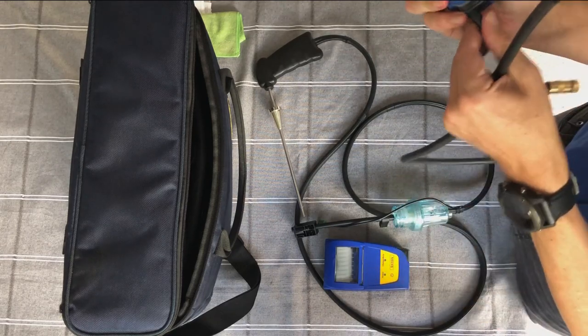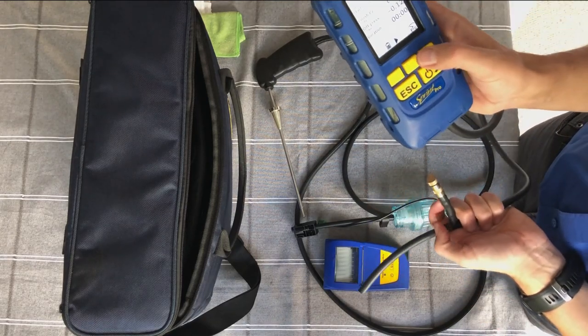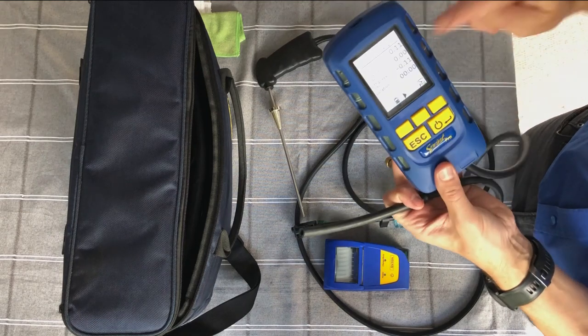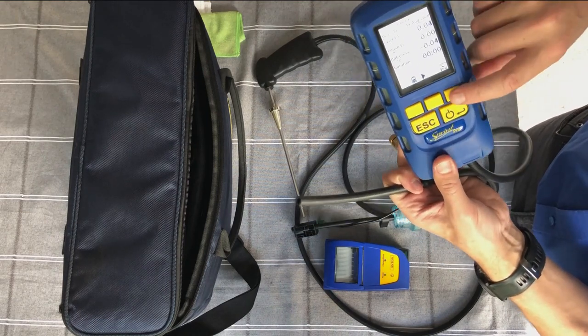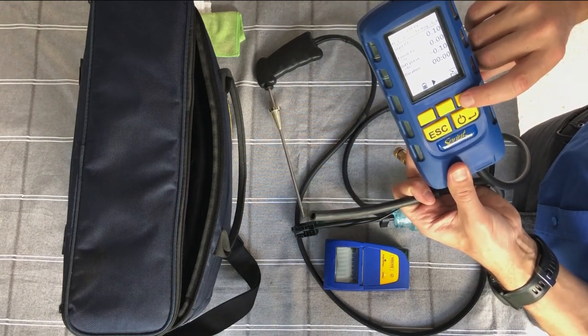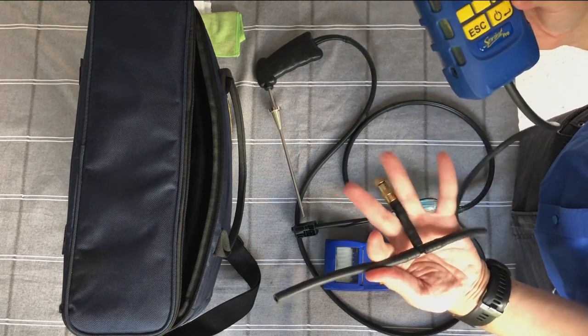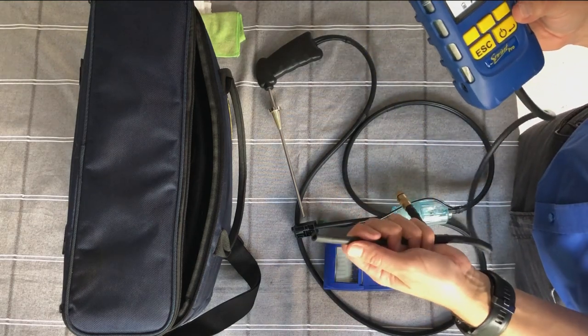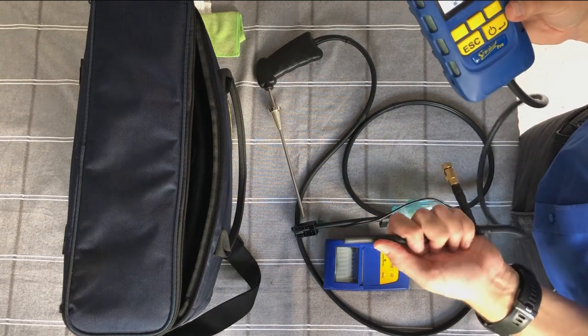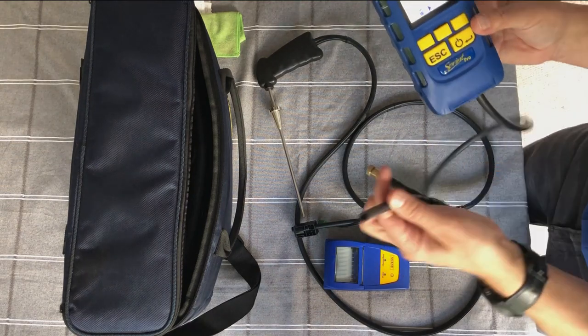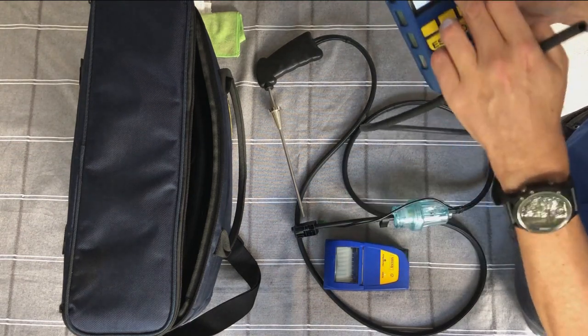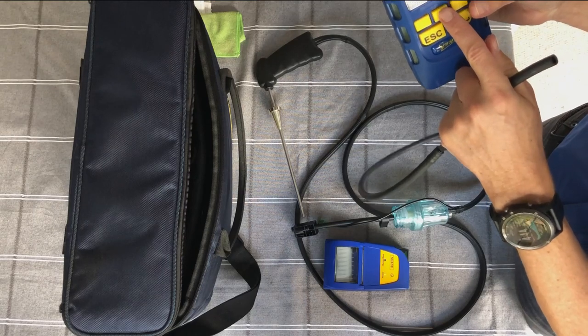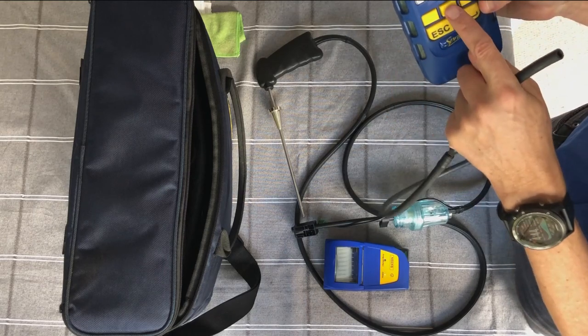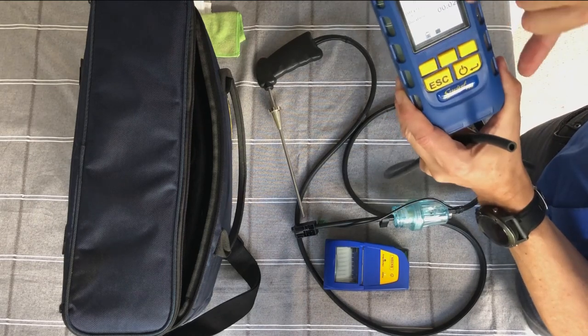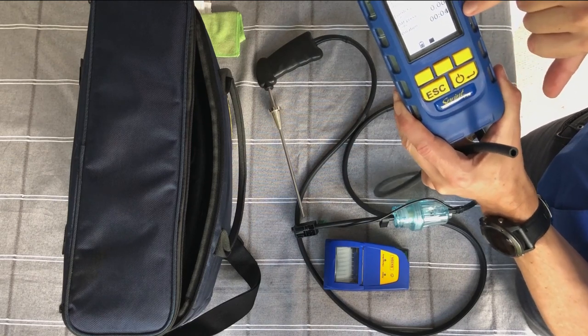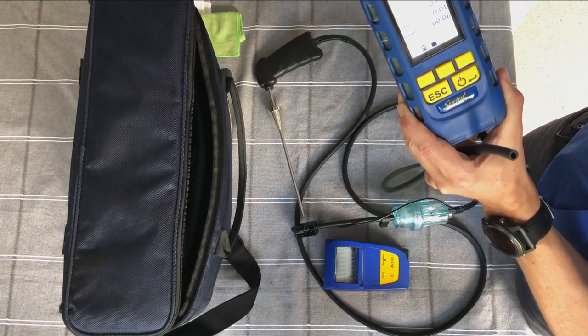So first thing, get that attached, go into let-by tightness test mode, and here we are. Again, you've got that pressure zero function before you start if you want to, so you can zero it in air like this. You all know how to do a let-by tightness test, I don't need to teach you that. But once you're set up and you've got your starting pressure, which is no pressure here because it's ambient, you press start and it's timed. The duration shows on the bottom there.